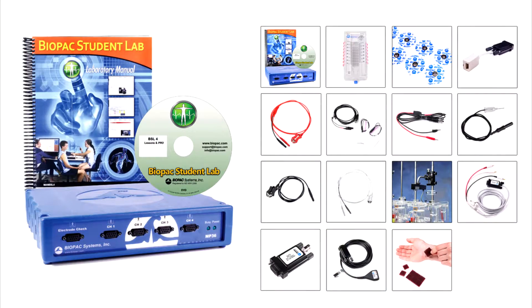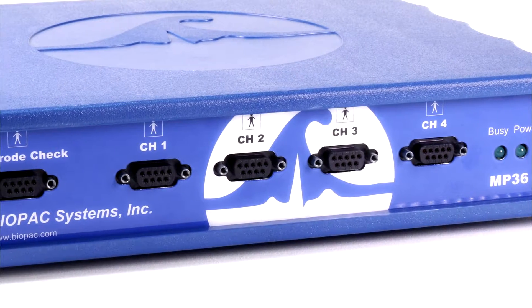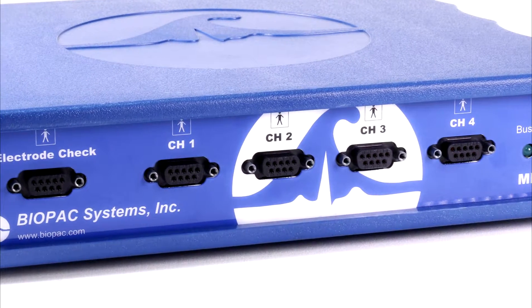This BSL system includes the following. The MP36 data acquisition unit. This is the heart of the Biopac Student Lab system. With four universal analog input channels, data can be recorded from a wide range of signal sources.